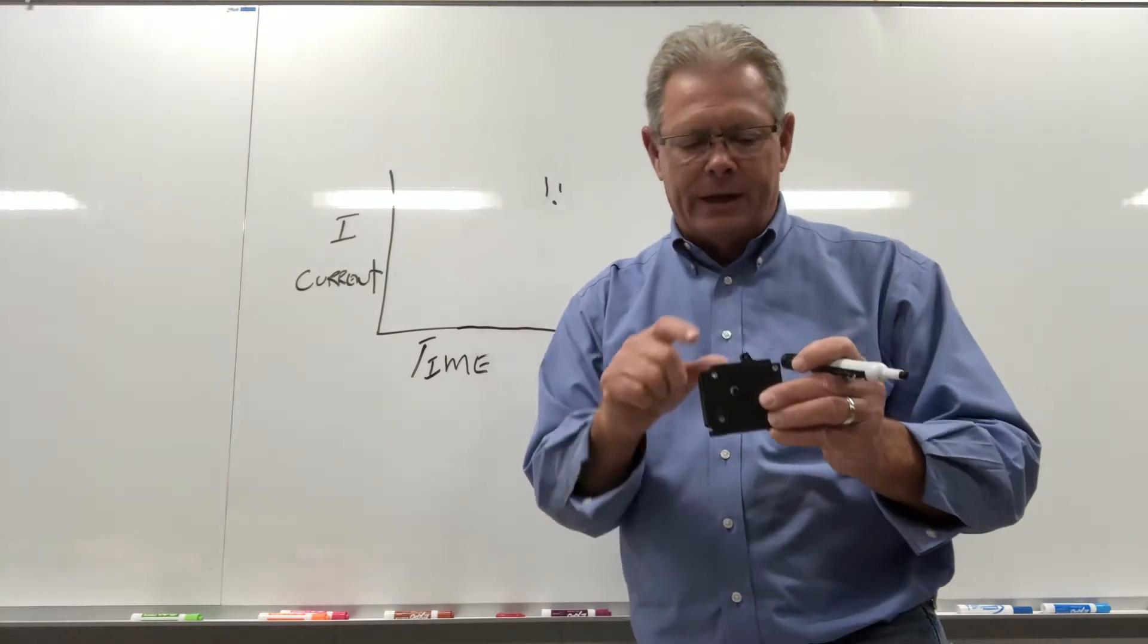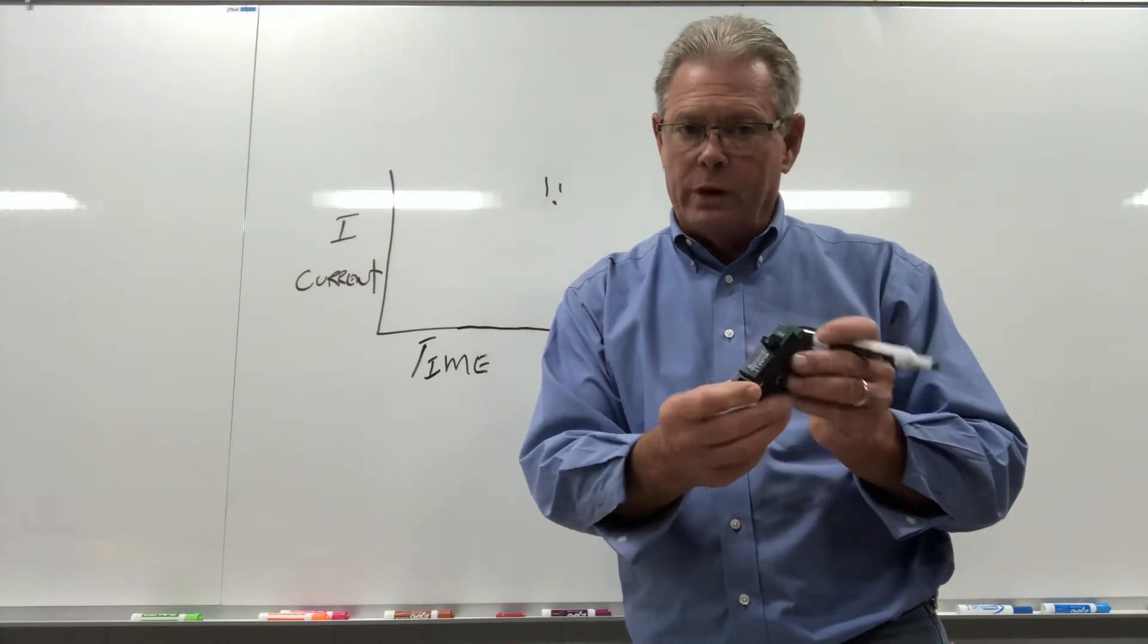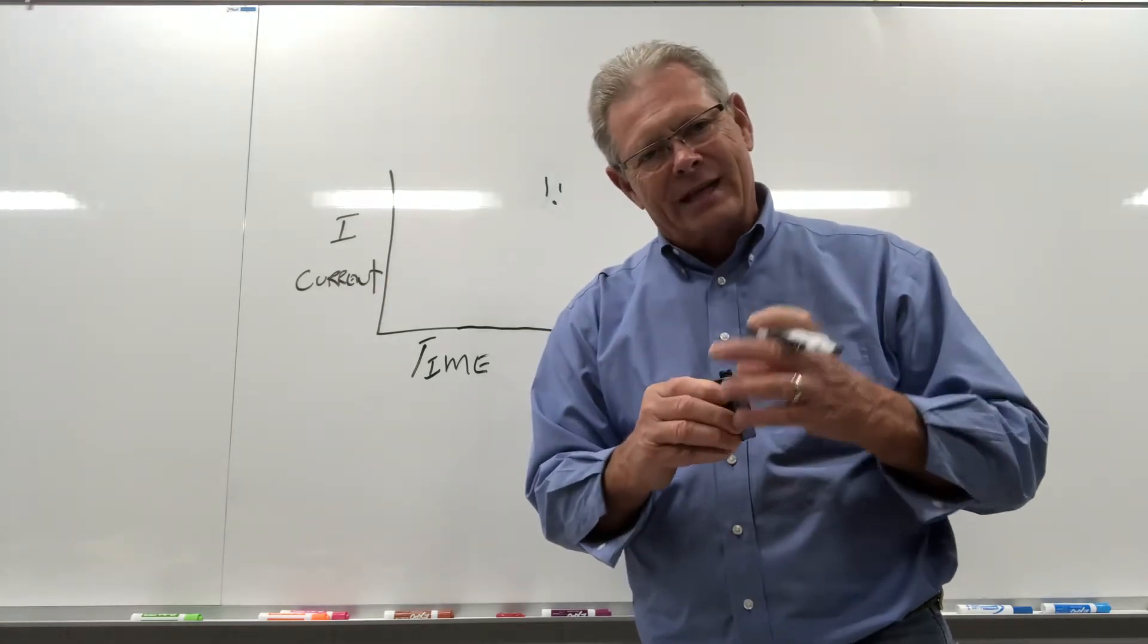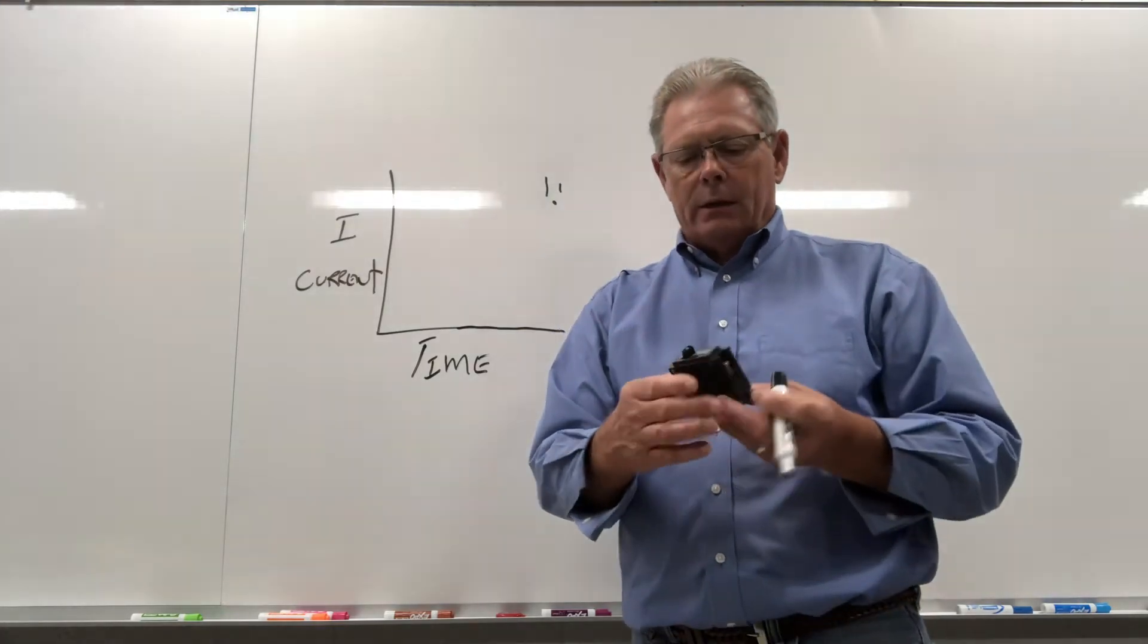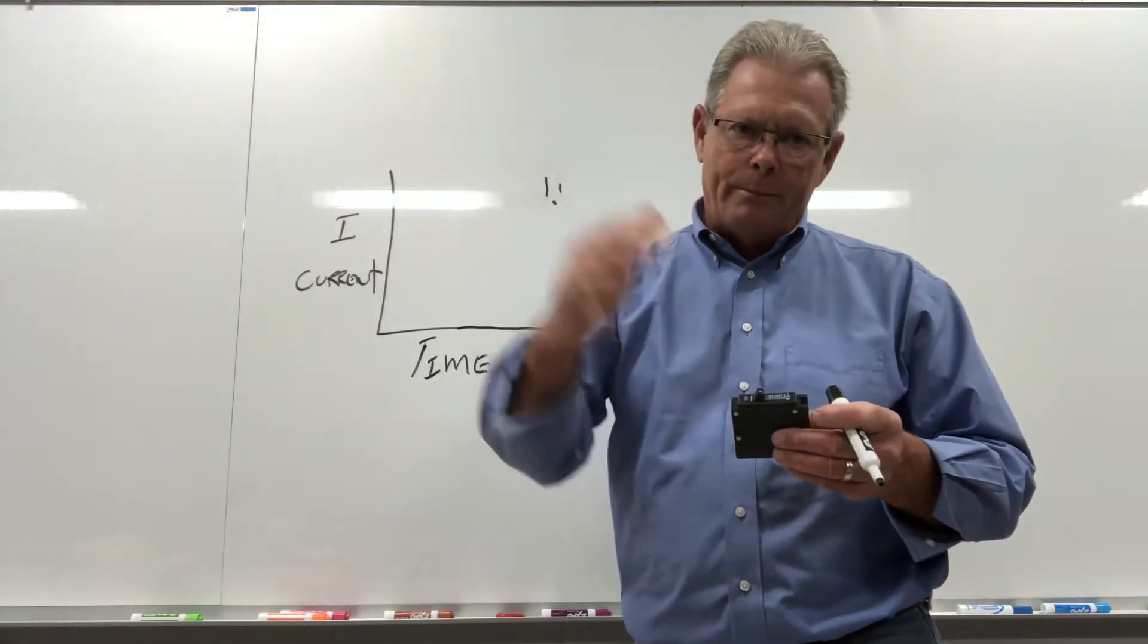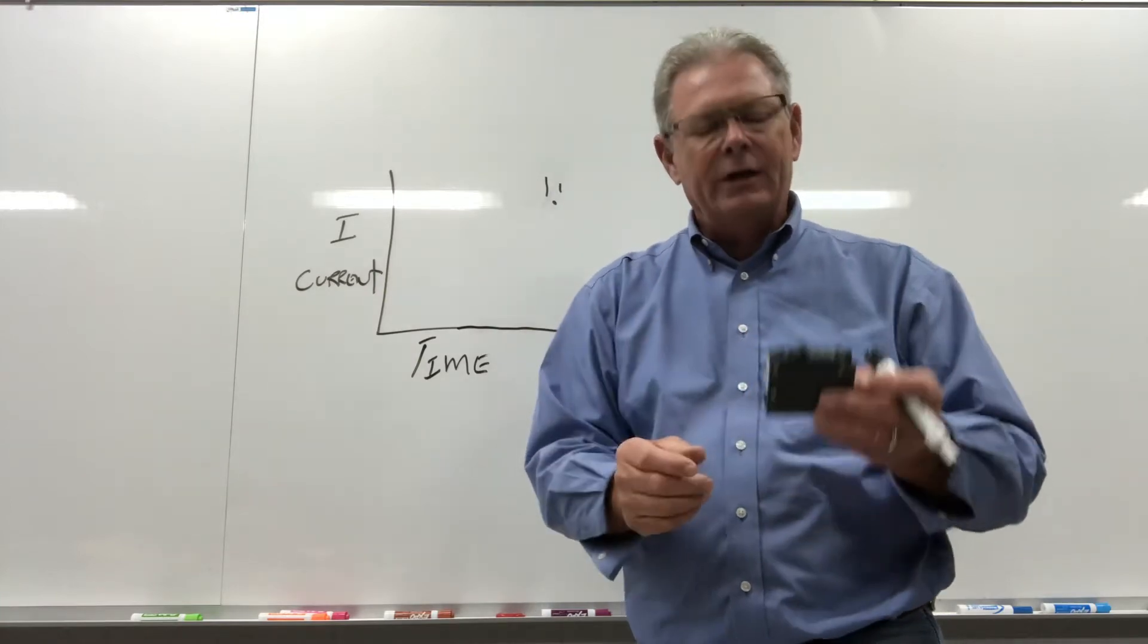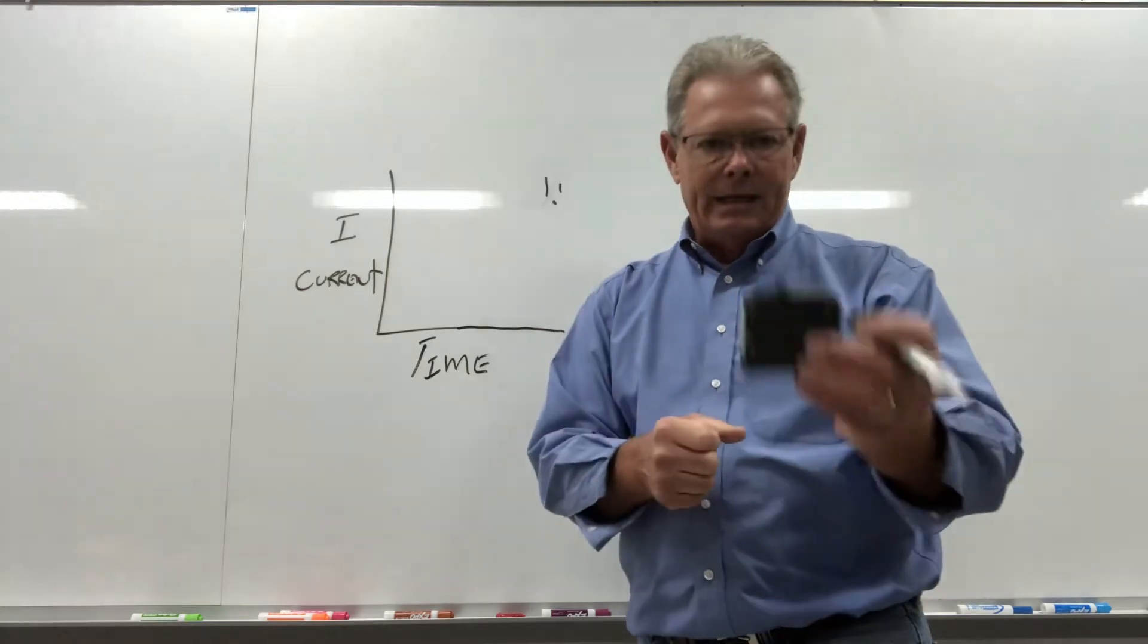And that's where you need an interrupting rating. This breaker has three ratings. The 15 amps is the standard rating. Then this is a 120-240, that's the voltage rating. Then if you look at the side of this, this is 10KA. So it has a 10,000 amp instantaneous current rating or interrupting rating. Whenever the power company makes your overhead drop or your underground lateral into your house, they size the transformer and size the wire size for your feeders so that you'll never see over 10,000 amps under a dead short condition in your house.